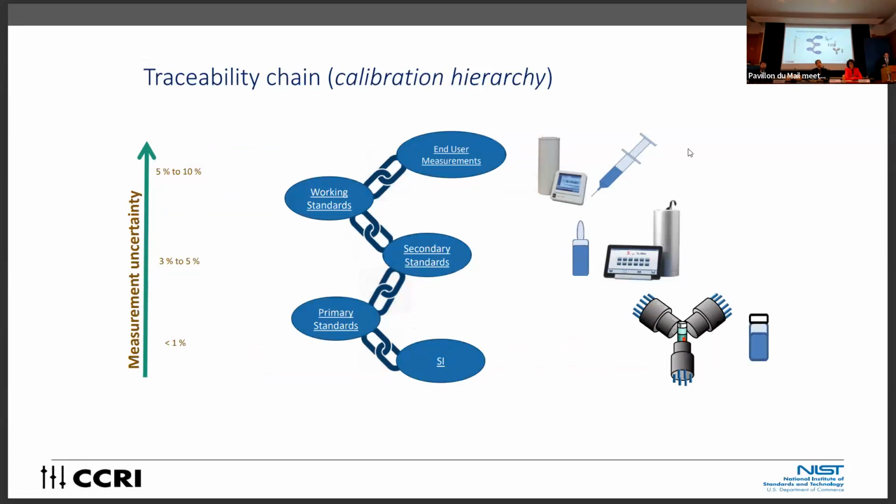you're adding on uncertainty. On the left-hand side, you see what we've typically seen for a primary standard: a National Metrology Institute or a designated institute would typically have a standard uncertainty of about 1%. Then at the secondary standard level, and at the working standard level, that typically adds a factor of 3 to the uncertainty, depending on the technique and the capabilities of the laboratory.